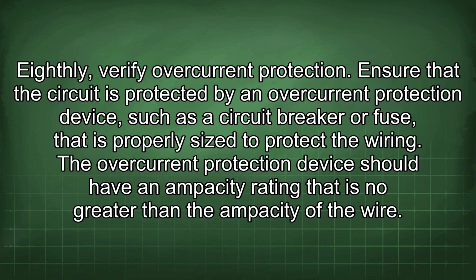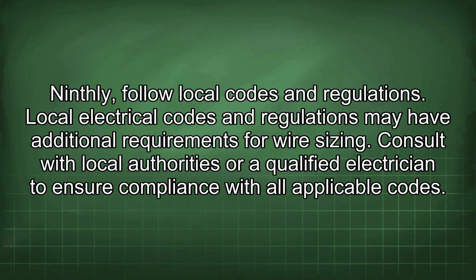Eighthly, verify overcurrent protection. Ensure that the circuit is protected by an overcurrent protection device such as a circuit breaker or fuse that is properly sized to protect the wiring. The overcurrent protection device should have an ampacity rating that is no greater than the ampacity of the wire. Ninthly, follow local codes and regulations. Local electrical codes and regulations may have additional requirements for wire sizing. Consult with local authorities or a qualified electrician to ensure compliance with all applicable codes.